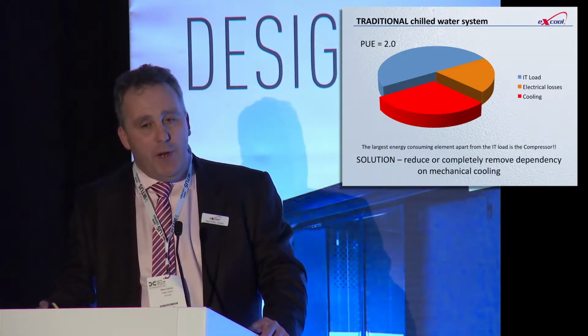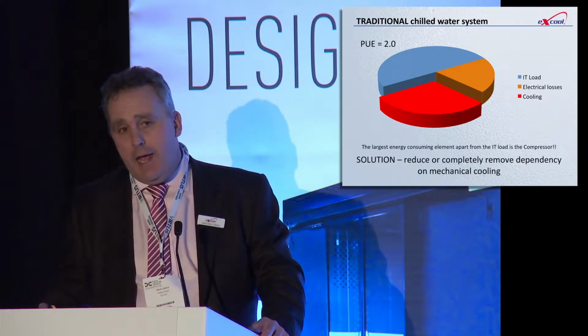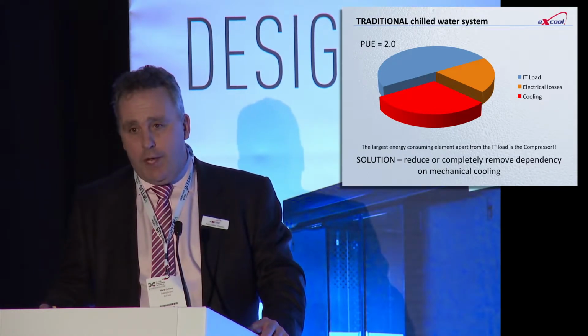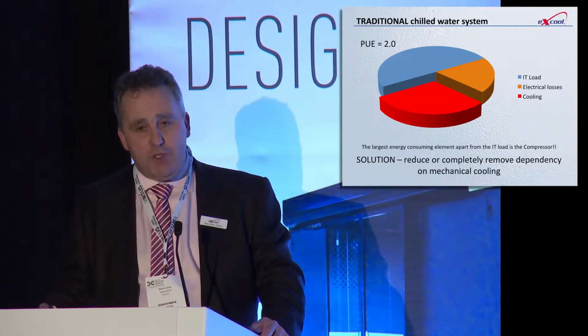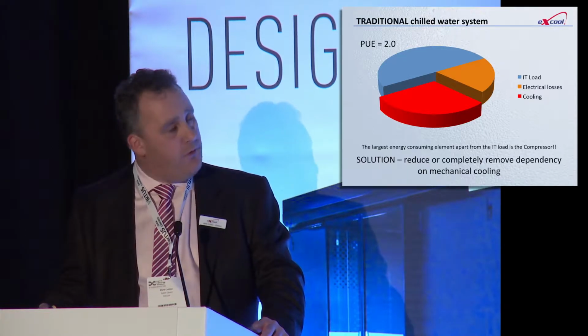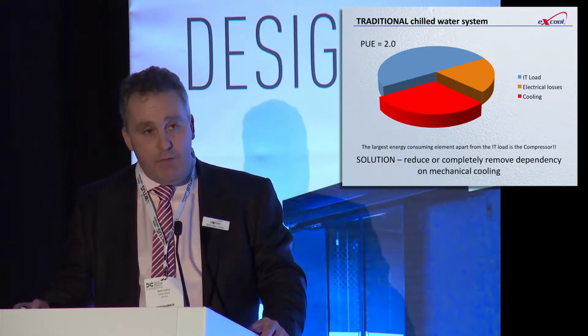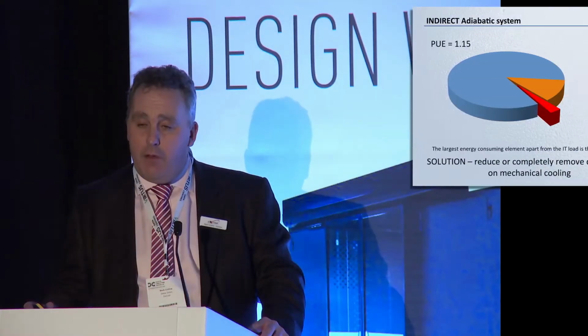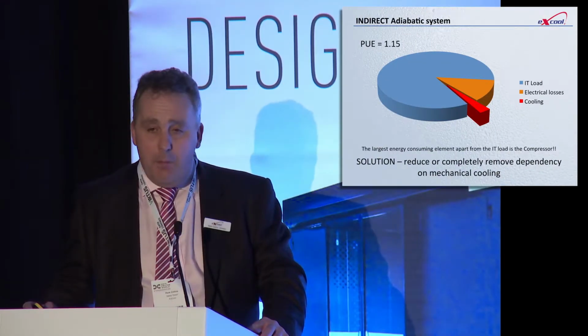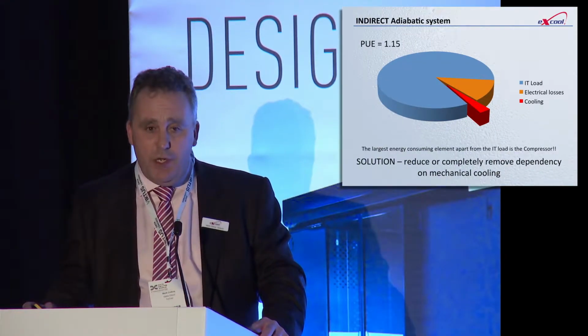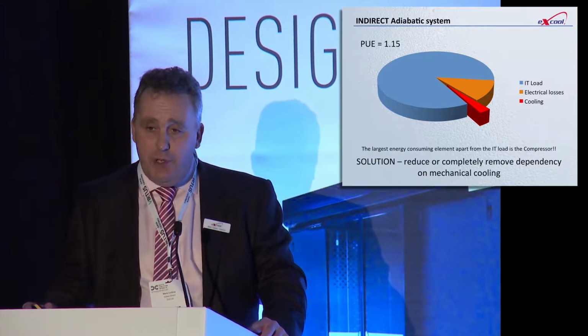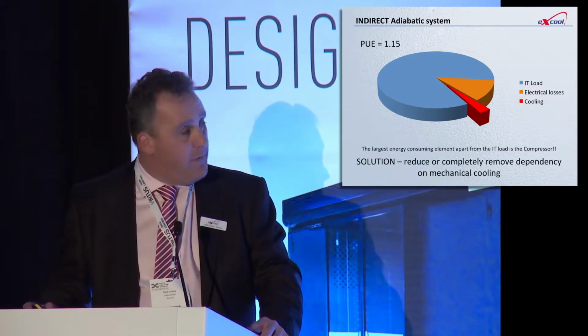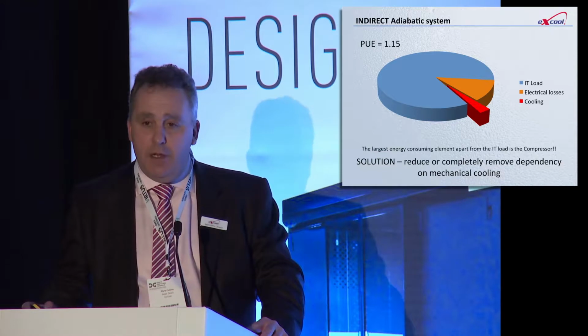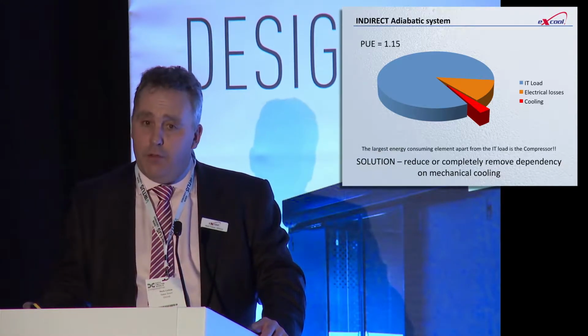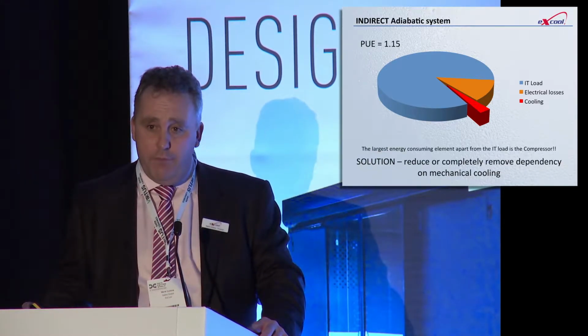Now, we want to eliminate that as much as possible, and in the data centers that we are working on today, several in this country and others throughout the rest of Europe, we're achieving PUEs that are far lower than 2. And the main reason for doing that is because we're using outdoor air as a cooling medium. We're only pushing air around the space, and we're removing the need for compressors throughout all of those.